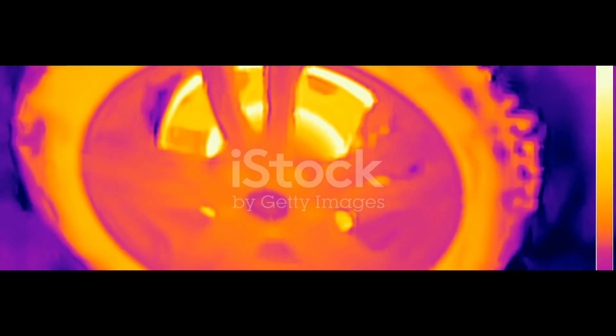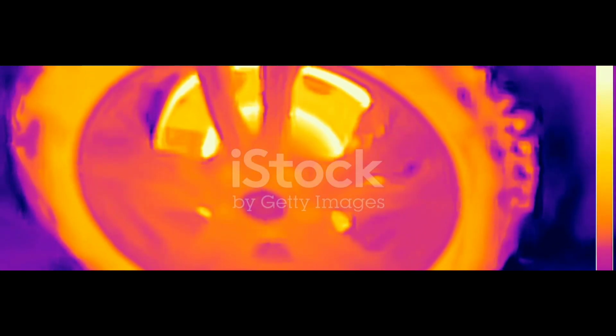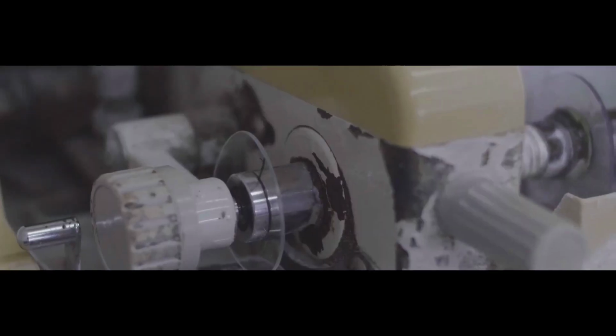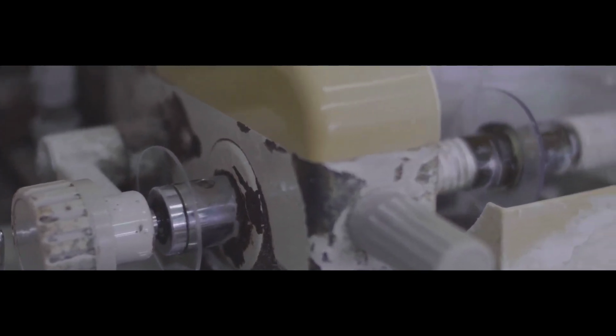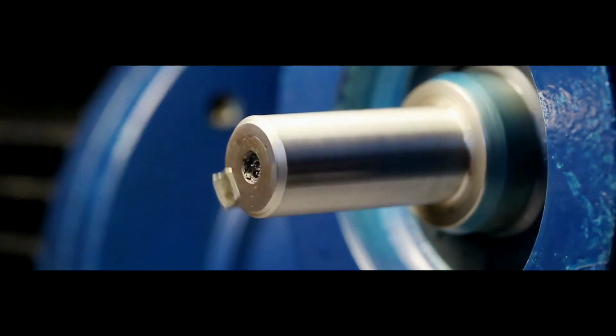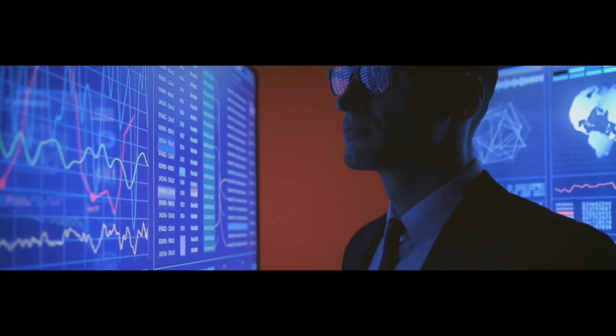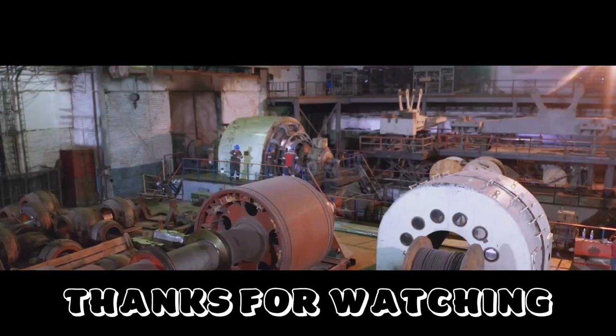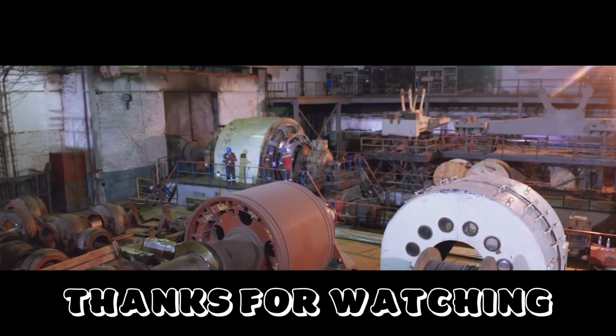No machine is perfect. Energy is always lost. Copper losses, I²R, turn current into heat in the windings. Iron losses, hysteresis, and eddy currents waste energy in the armature core. Laminated steel cores help reduce these losses. Mechanical losses come from friction and air resistance. All these losses add up, lowering efficiency.